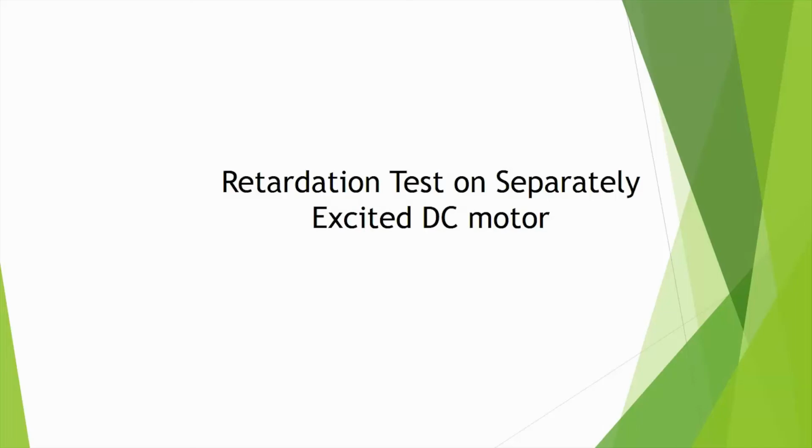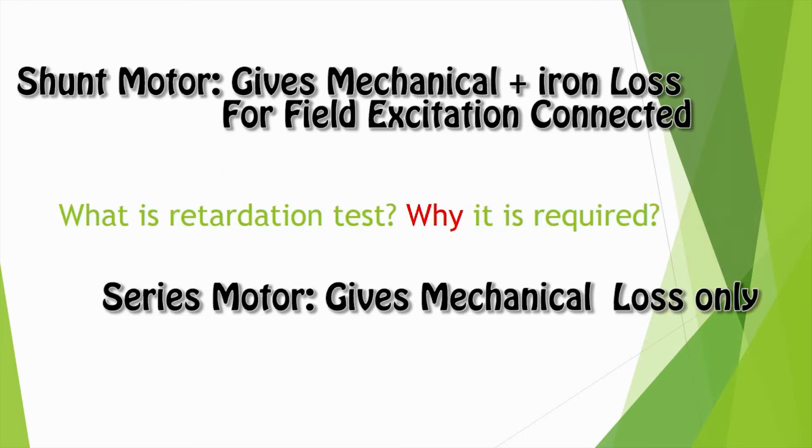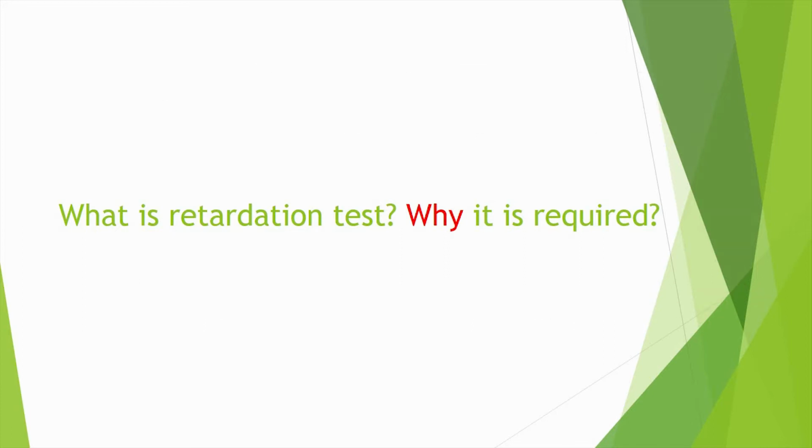Hello everyone, today we are going to discuss the retardation test on a separately excited DC motor. What is the retardation test and why is it required? The retardation test is performed on the DC motor to find out the stray losses. Stray loss is the combination of mechanical and iron loss, and the mechanical losses include frictional and windage loss.